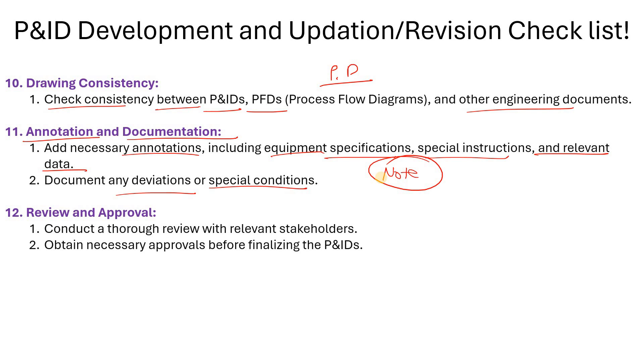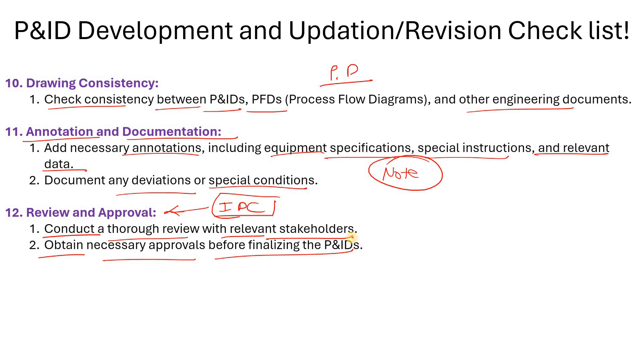Please follow a proper review system in your company, like the IDC process. The draftsman prepares the P&ID, then you check it as an engineer, then show it to your manager, senior manager, or HOD. Release it for internal review to all departments — piping, mechanical, instrumentation, electrical, and civil — so they can check it. Incorporate necessary comments and then proceed to release to the client. Conduct a thorough review with relevant stakeholders and obtain necessary approvals before finalizing the P&IDs.